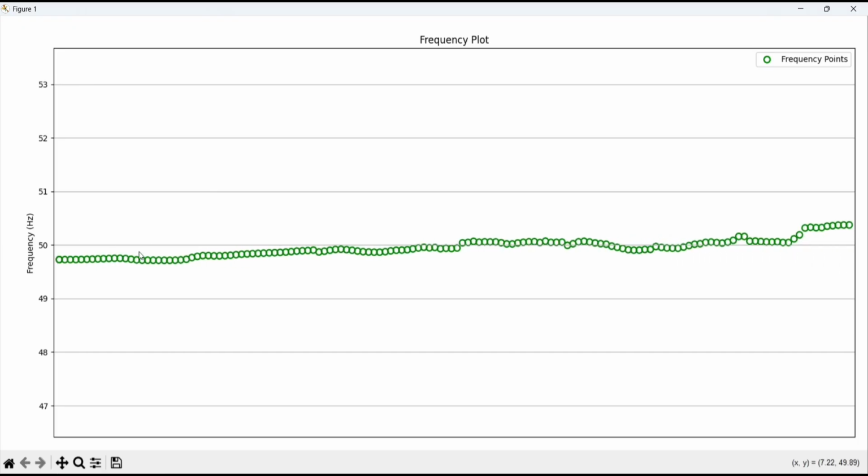Based on the battery supply, the wind speed and the wind farm power production, the battery is working, and nearly constant power is supplied to the grid, so nearly constant frequency is available throughout the day, like with the hydrogen storage system. Here you can see a nearly linear 50 Hz graph throughout the day.